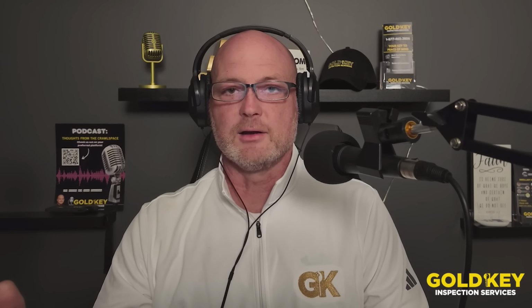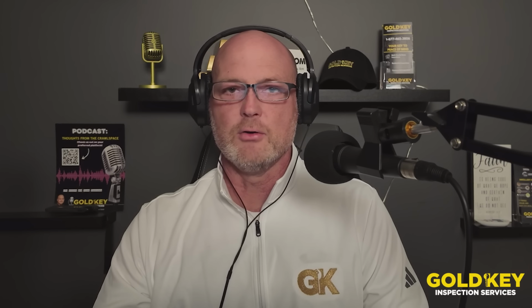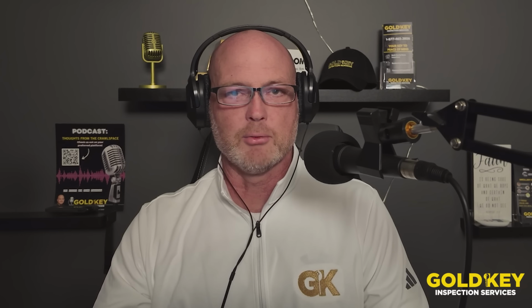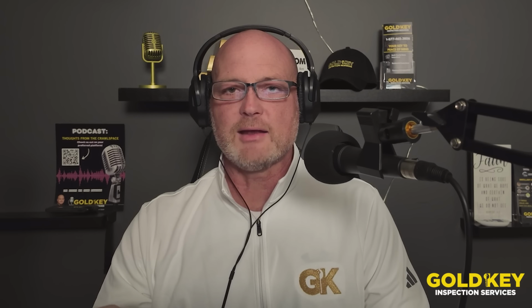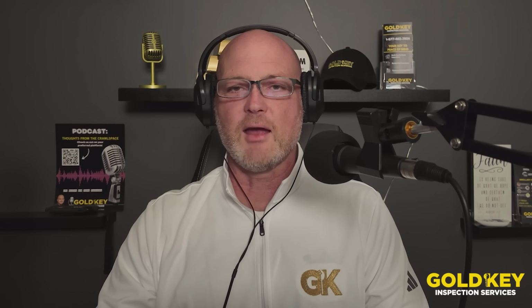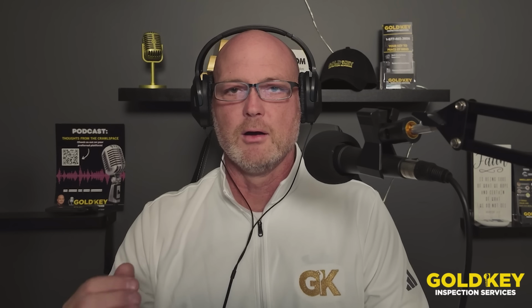Another issue that is crucial for your air conditioner is an electrical disconnect. An electrical disconnect is the power source for that air conditioner, and this is required to be within a line of sight, generally no more than 6 feet away from the air conditioning unit. This can't just be a breaker inside, this needs to be outside. Well, why is this? Well, if a technician comes to work on it, he needs to have total control over the power on that unit.